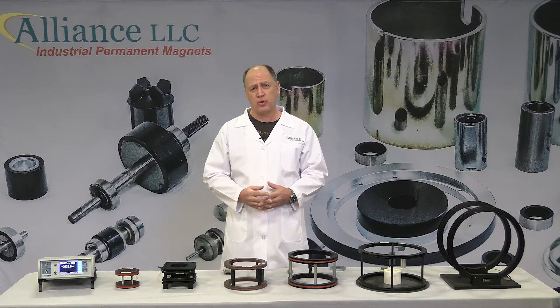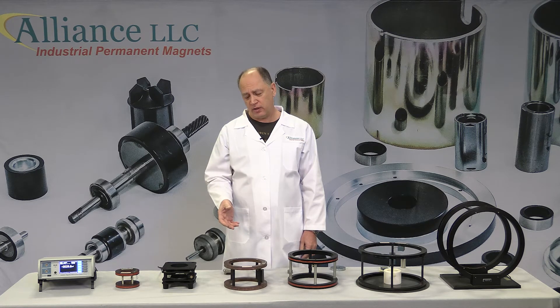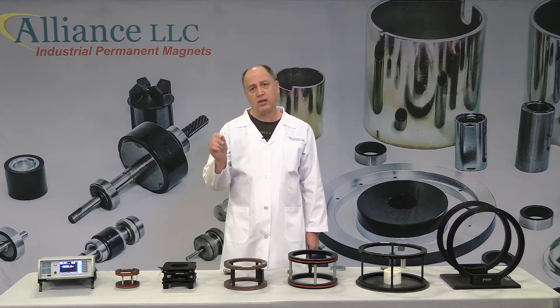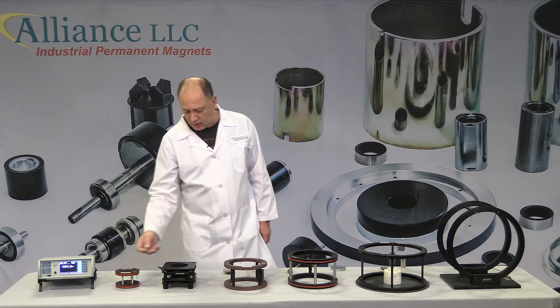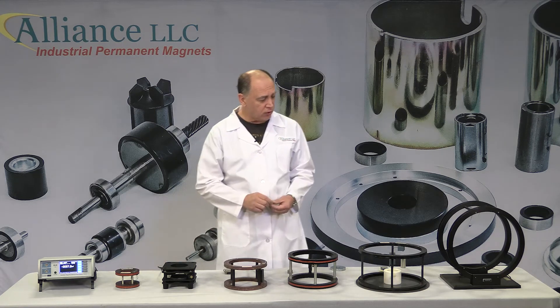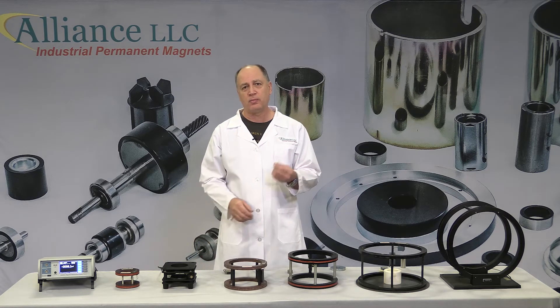When purchasing a Helmholtz coil, it's important to know the size of the magnet being tested. The coil diameter needs to be at the very minimum three times the dimension of the magnet, and the height of the coil is one half the distance of the diameter. So if you're measuring a magnet that is around a quarter of an inch, you would need a coil that's about this size right here, which is about two inches in diameter. You can go larger to maybe three inches, but if you try to use a coil that's eight inches in diameter for a small magnet, the signal will be so weak that it will be barely measurable.